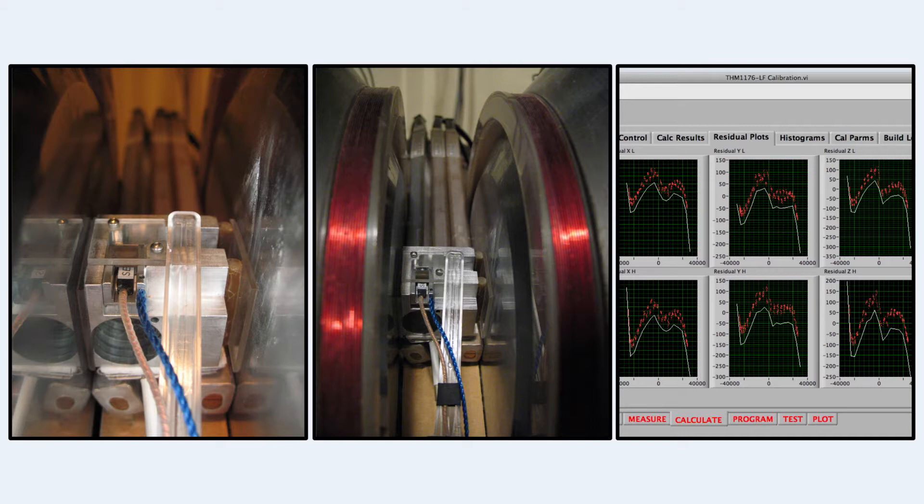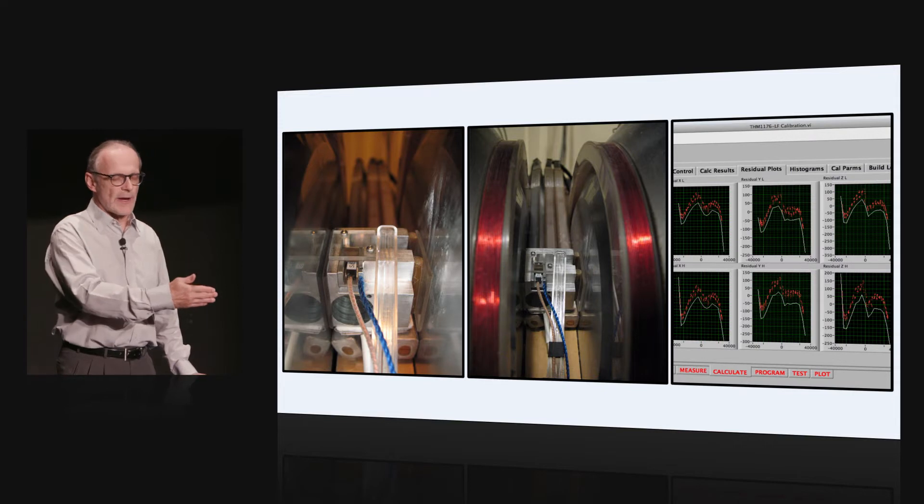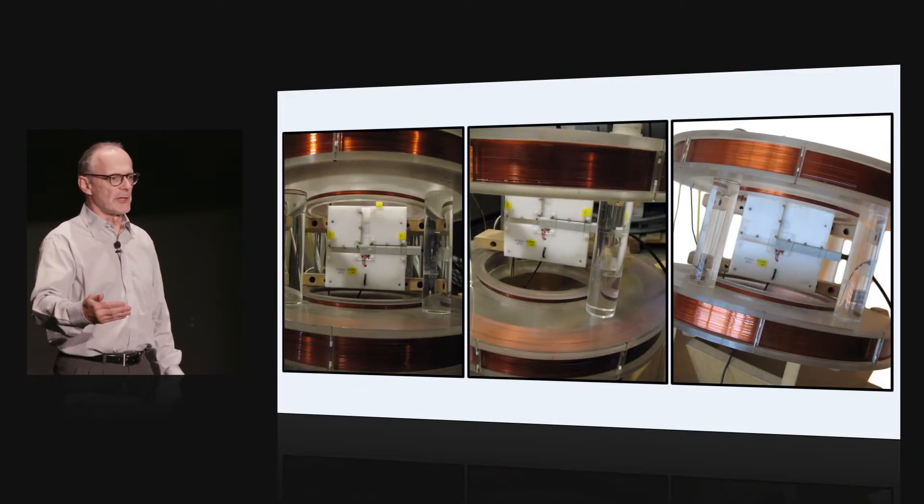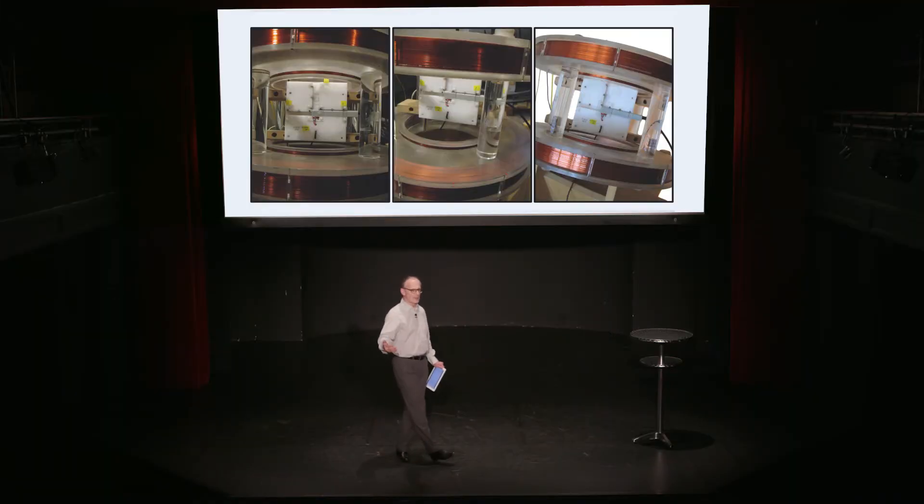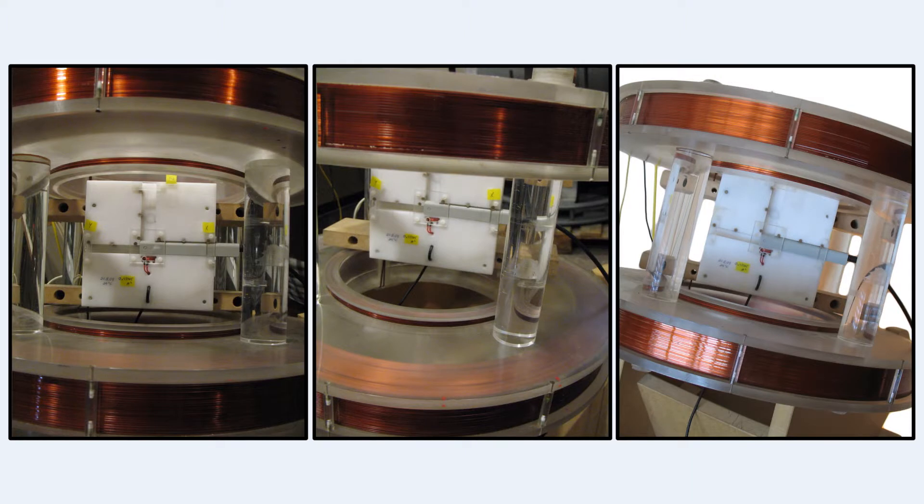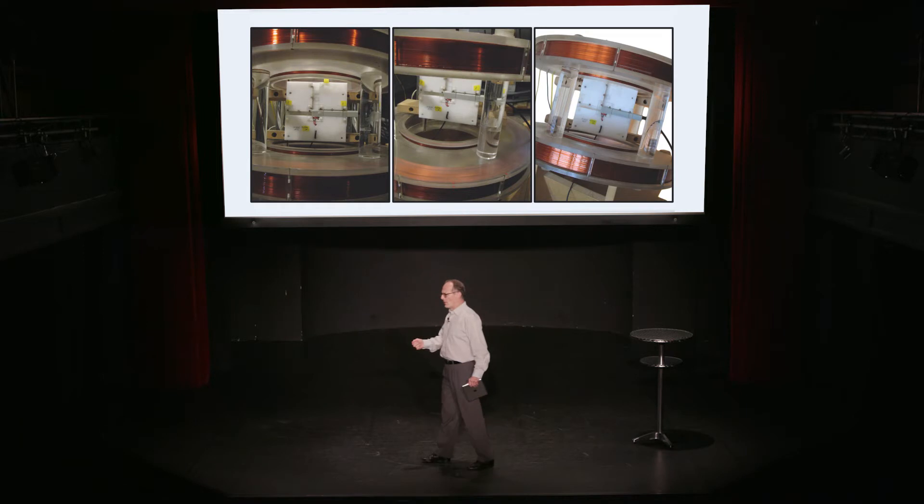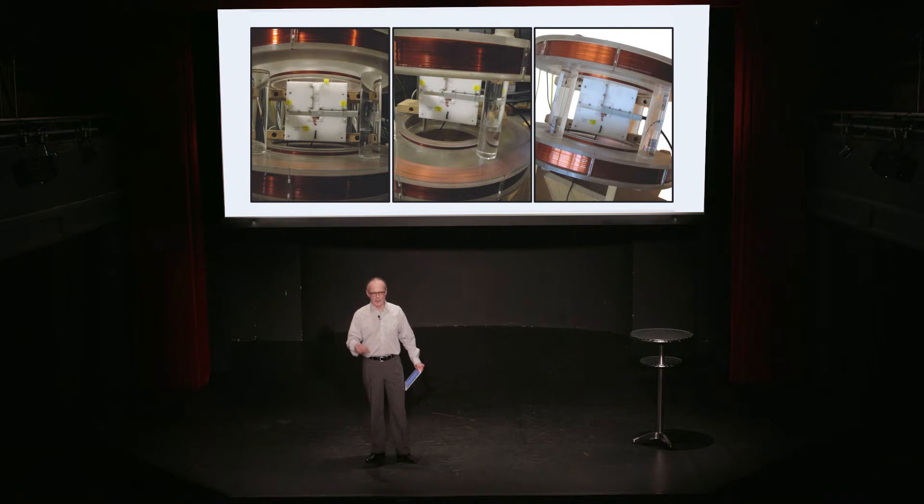And this entire calibration procedure needs to be repeated regularly every year or every 18 months to correct for aging of the semiconductor material, for example, as the dopants diffuse through the semiconductor material. So, as you can see, these benefits of the Hall sensor, they're kind of relative. You have to pay for them with lots of very good calibration.